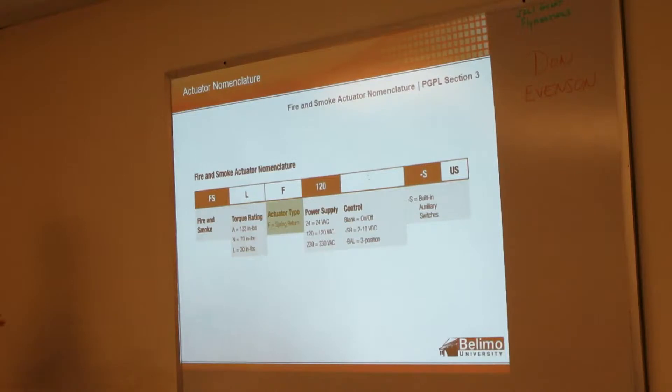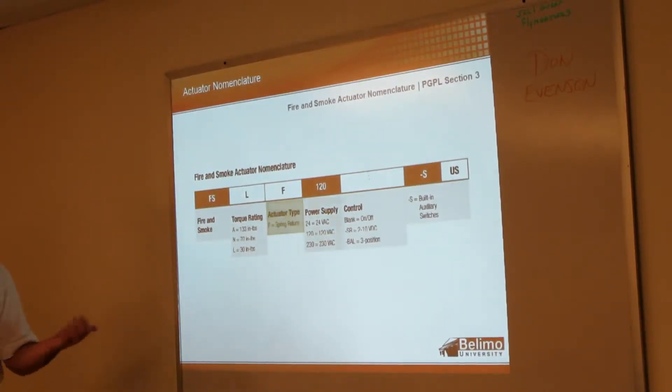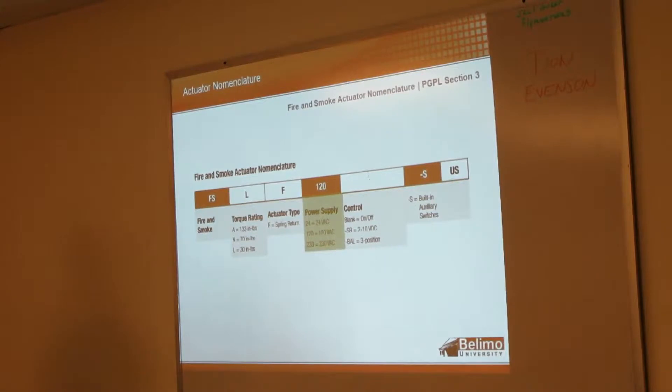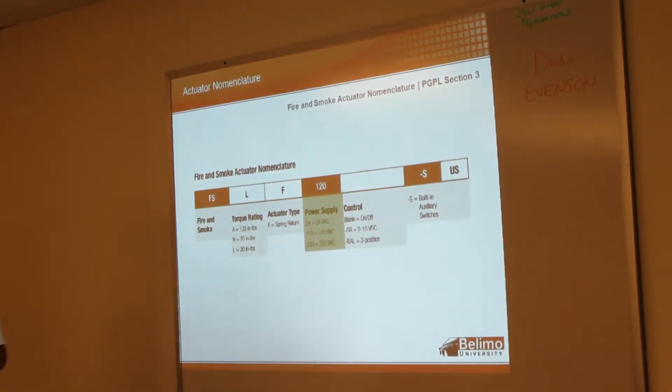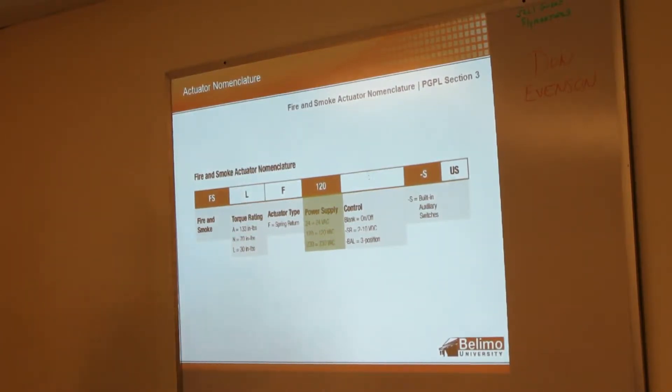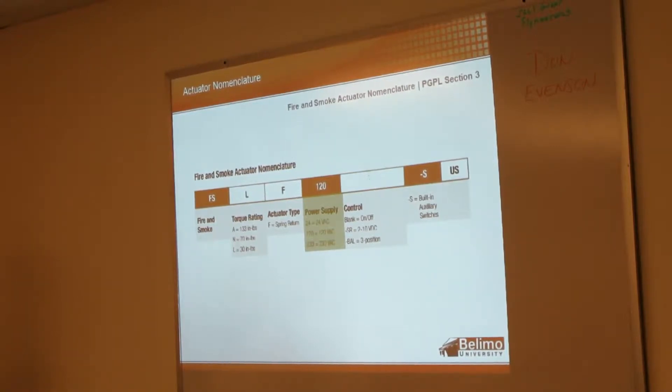All the fire and smoke actuators have to be spring return. That's part of the life safety initiative. For power supply, we've got 24 volt, 120 volt, and for Europe we've got 230 volt. One question I get quite a bit is which do we sell the most of? It's really split about 50-50 between the 24 and 120 volt.